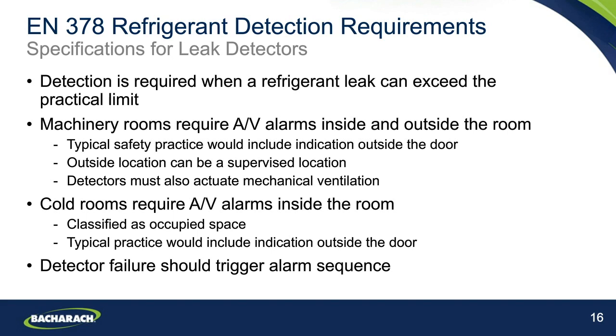As we just mentioned, cold rooms in the EN 378 standard require audio-visual alarms inside the room. The classification there is as an occupied space and would be category C within those occupancy classifications. Although it's not mandated, we would typically expect to see an indication outside of the cold room door in the event of a leak as well, even though it's not mandated by the regulations. And of course, as we mentioned, the detector failure should trigger the alarm sequence.